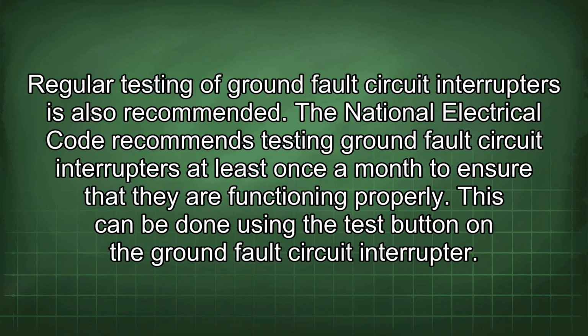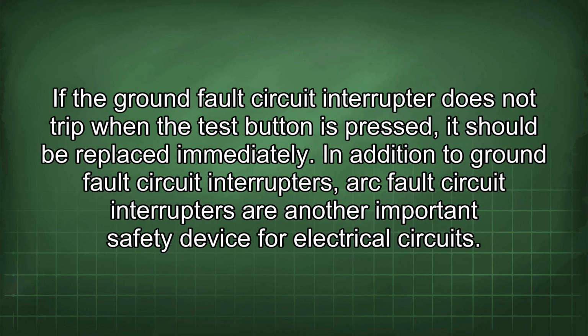Regular testing of ground fault circuit interrupters is also recommended. The National Electrical Code recommends testing ground fault circuit interrupters at least once a month to ensure that they are functioning properly. This can be done using the test button on the ground fault circuit interrupter. If the ground fault circuit interrupter does not trip when the test button is pressed, it should be replaced immediately.